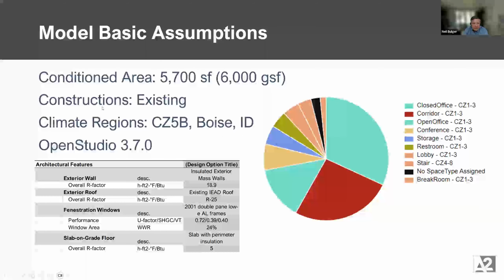I did put it in Boise. It is an existing building, so we stuck with the envelope that they had built up over time, which was more of a mass wall that had decent insulation, a lower insulated roof, R25. Some decent windows, not the best windows, but again, kind of what we've seen. This is a building that's built in California, so it's pretty typical for a 2001 construction building. A lot of open space, a lot of corridor space kind of between rooms. There's a shaft, I think, in the building that's this no space type that I assigned here.